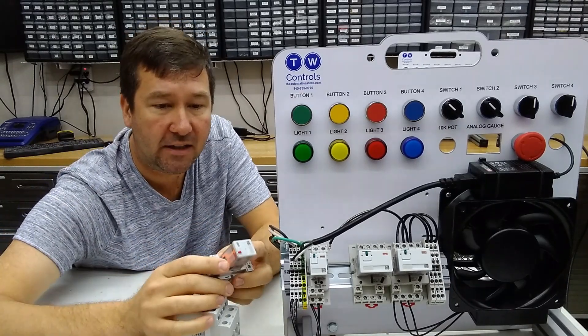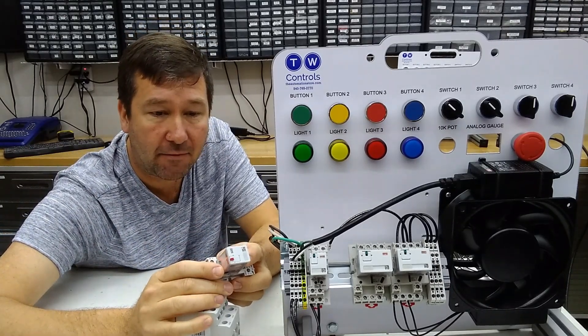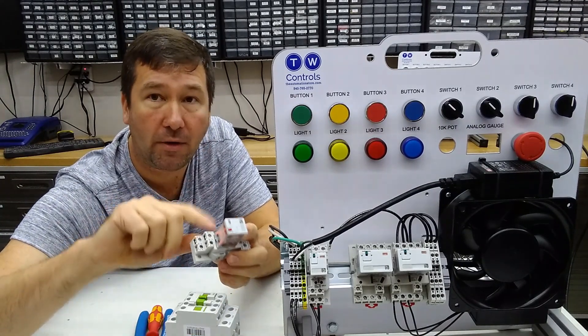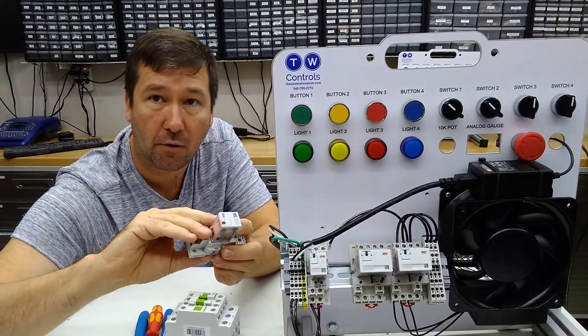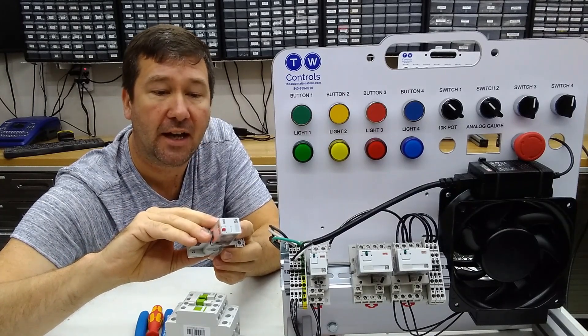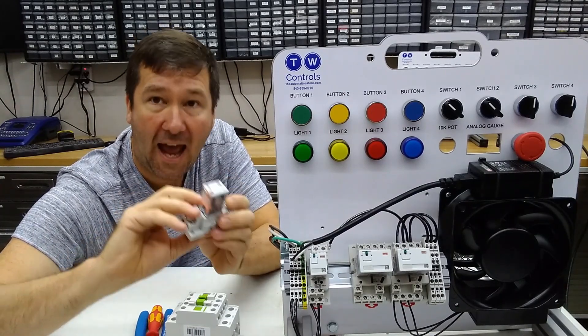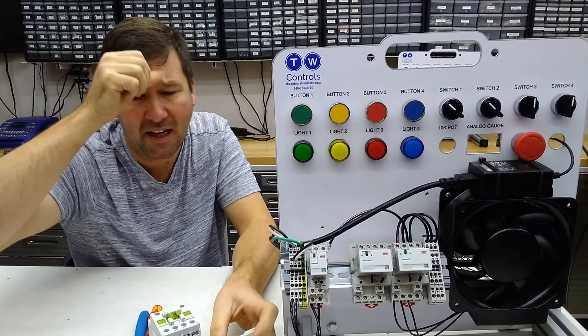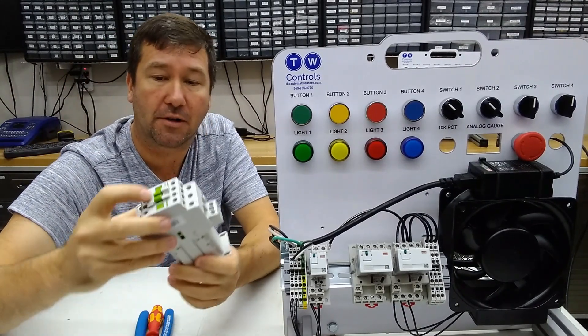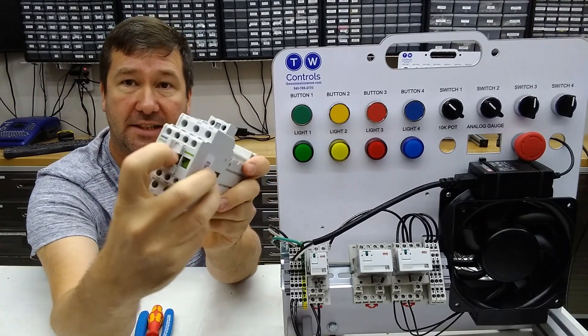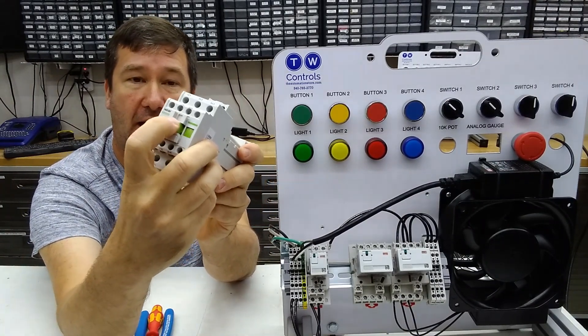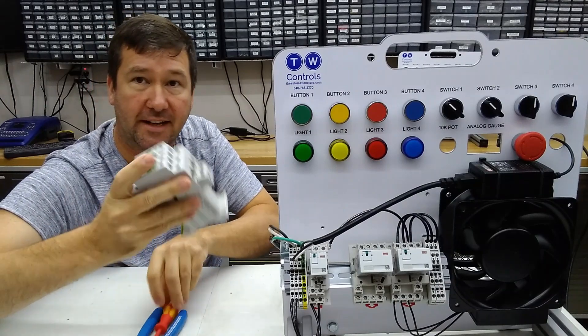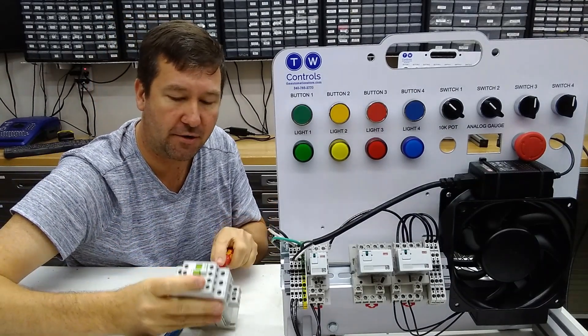Now if we look at this relay right here, it does have a horsepower rating. It is rated for only 120 volts as far as a motor load, and it is good for a half horsepower. So now let's talk about a little more about how a contactor works. You see on the front of it, when you energize a contactor, this thing moves in and out. But how does that actually work? We're going to take this contactor apart to show you.